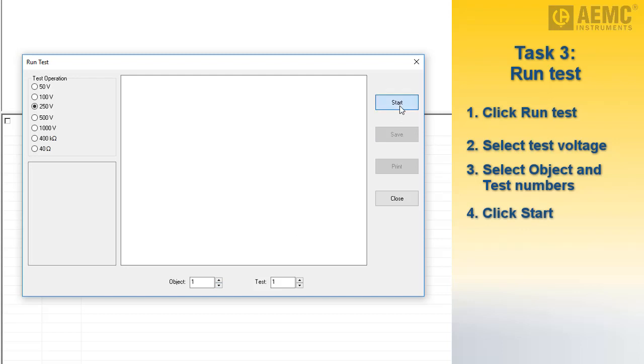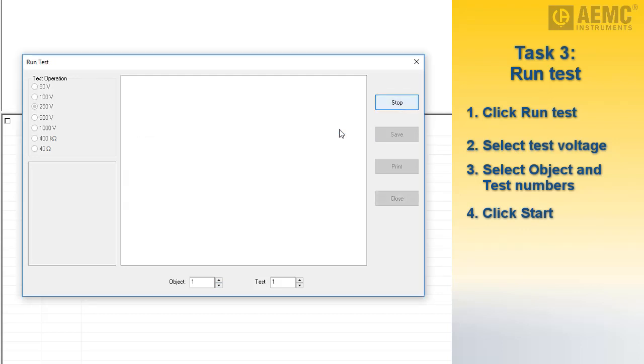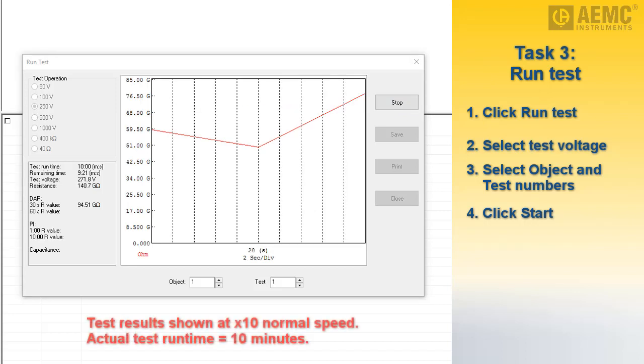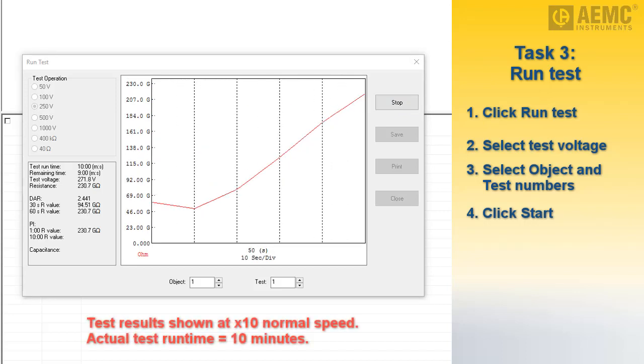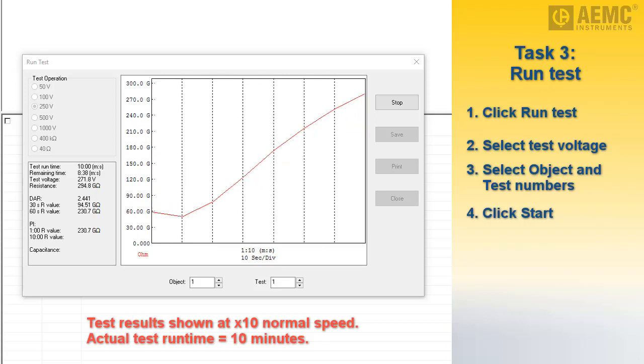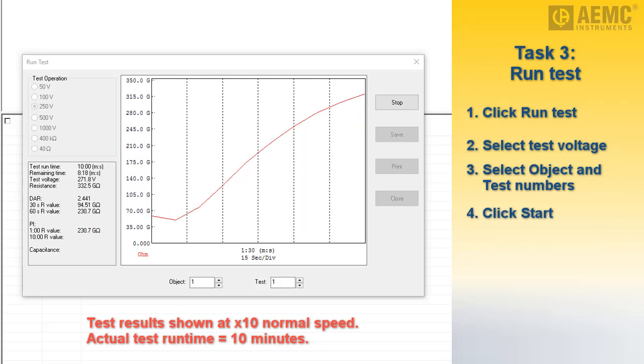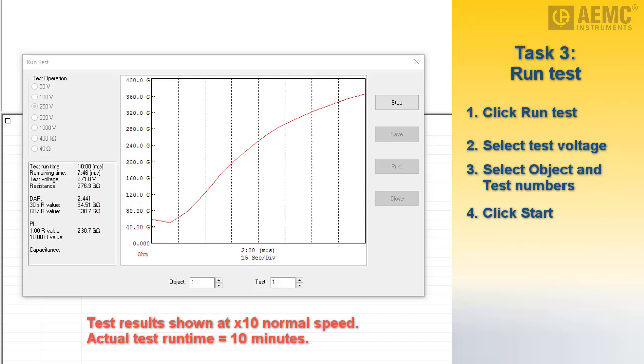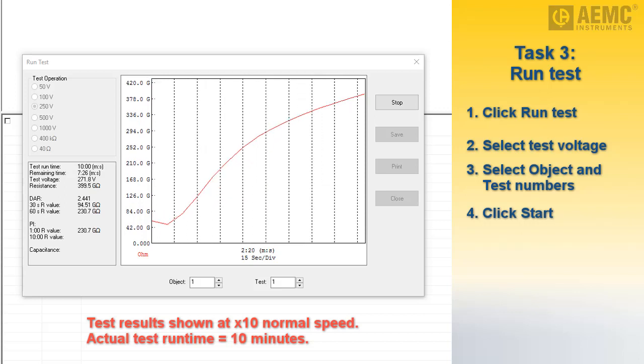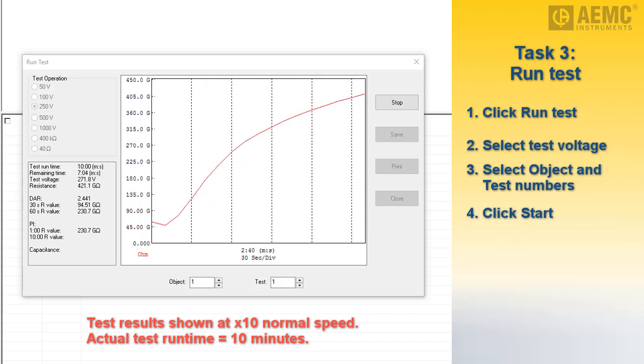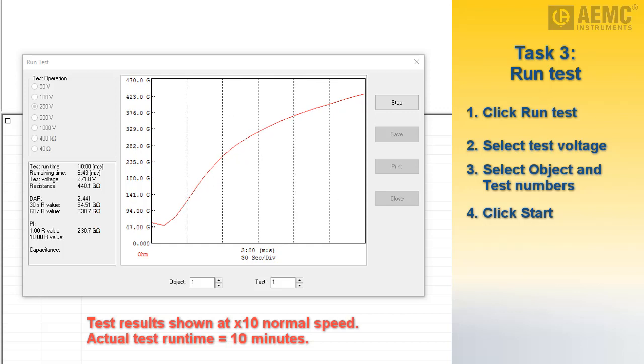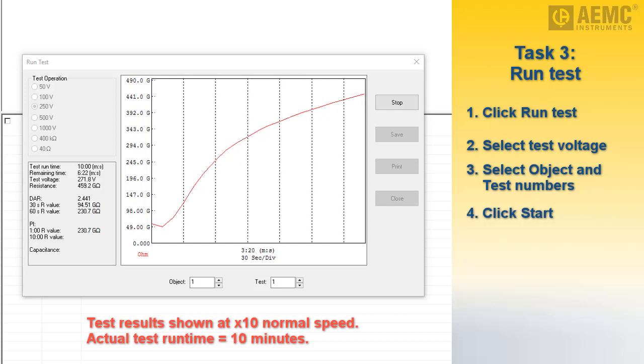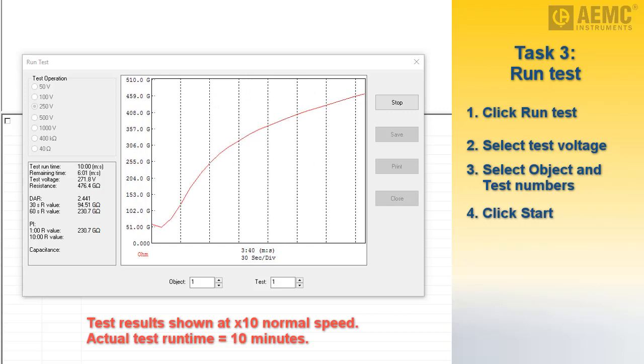After a few moments, real-time measurements are displayed as a graph in the center of the dialog box. In the lower left is a table showing the total duration of the test, the time remaining, the test voltage, most recent resistance measurement, and values for DAR, PI, and capacitance. The DAR value appears after one minute, while PI and capacitance will appear at the completion of this test.